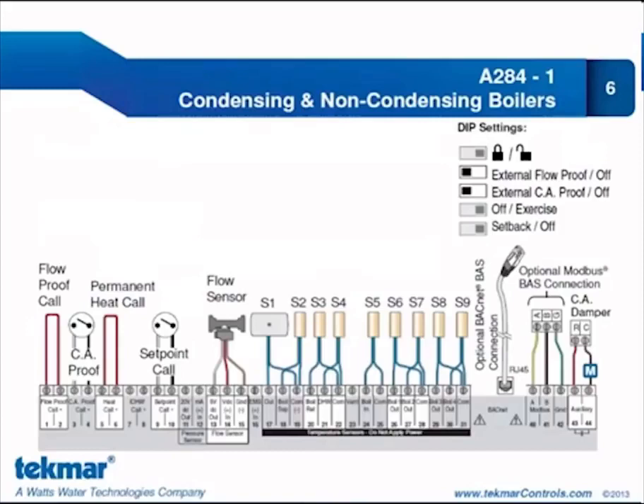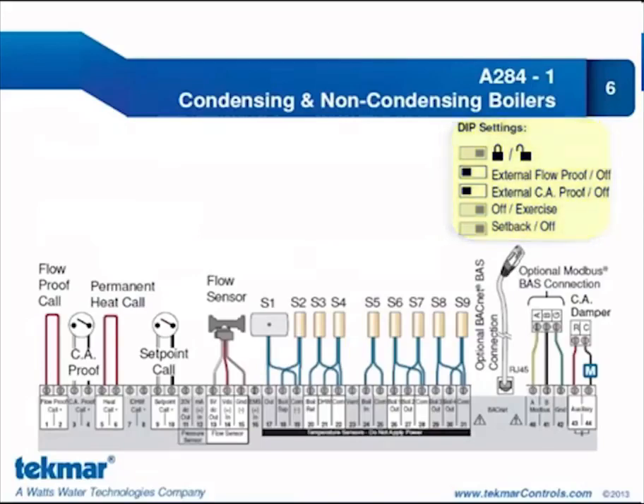Our flow sensor is a three-wire connection to the control, easy to distinguish because of reversed color coding from gray to white. The 284 supports an analog vortex-style flow sensor such as the Vortex series from Grundfos. Our other sensors include the outdoor sensor and eight sensors: the boiler supply sensor, boiler return sensor, boiler inlet sensor, and individual boiler outlet sensors. The DIP switches for external flow proof and external combustion air proof must be placed in the on position since we are doing both.